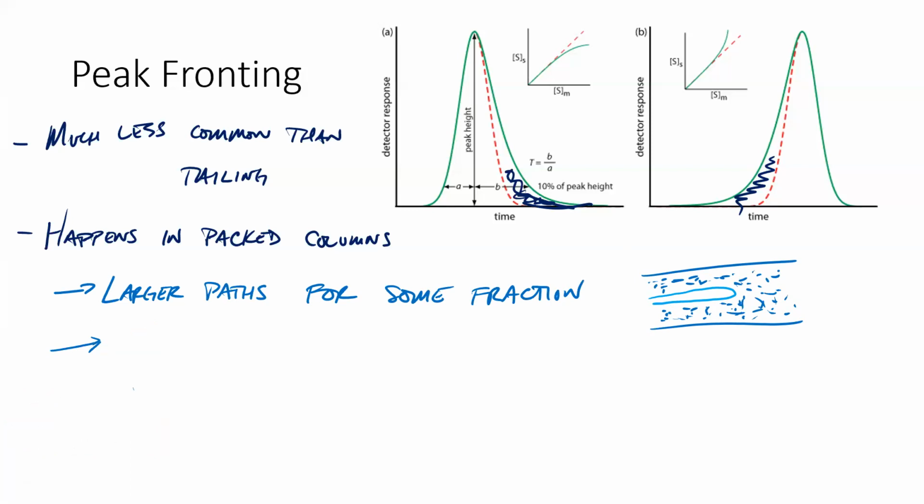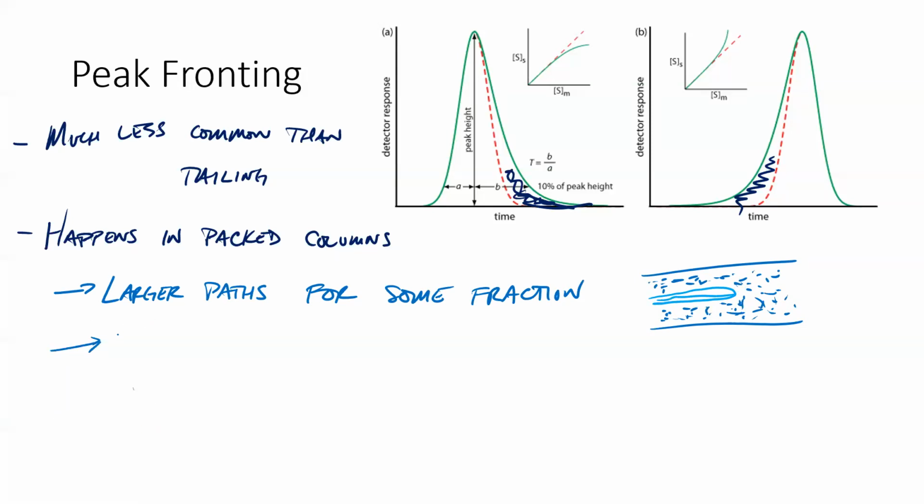And so before they really start slowing down and interacting with the stationary phase. Right? Another issue could be that the stationary phase, or really the stationary support, that column bed, has started to separate from the walls of the actual, that physical stainless steel wall surface.